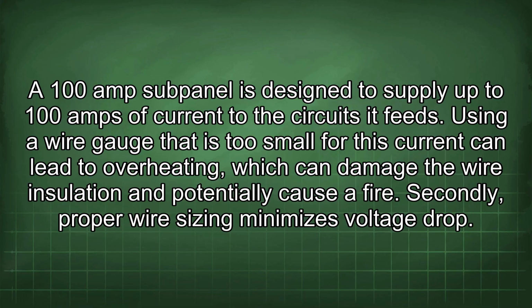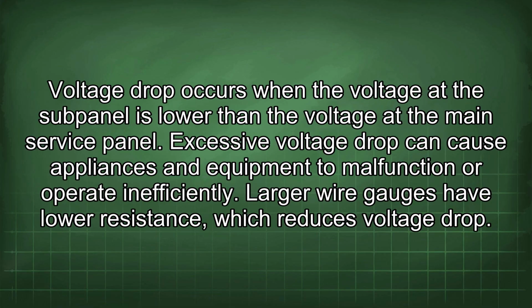Secondly, proper wire sizing minimizes voltage drop. Voltage drop occurs when the voltage at the subpanel is lower than the voltage at the main service panel. Excessive voltage drop can cause appliances and equipment to malfunction or operate inefficiently. Larger wire gauges have lower resistance, which reduces voltage drop.